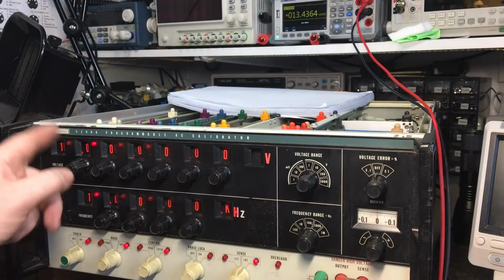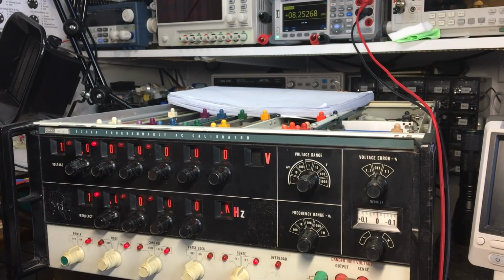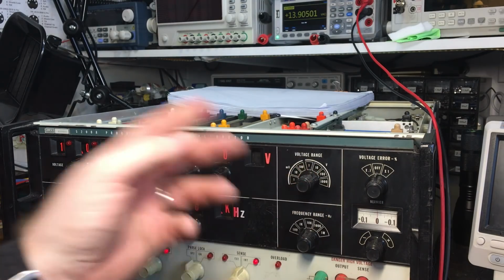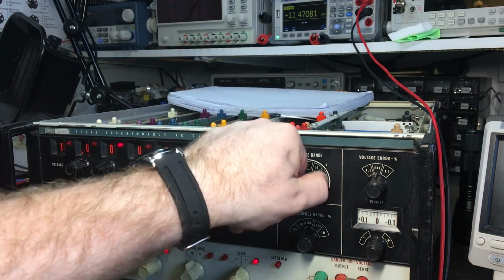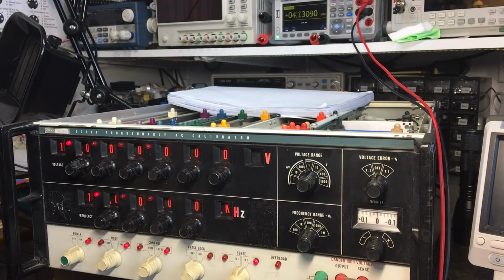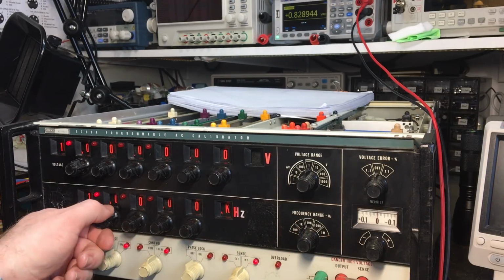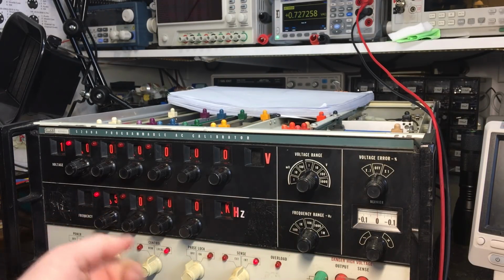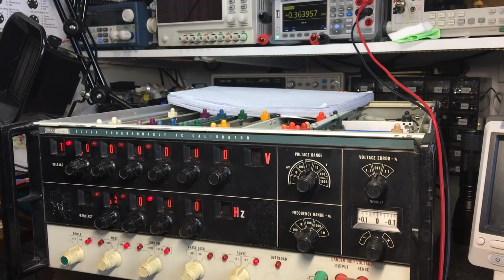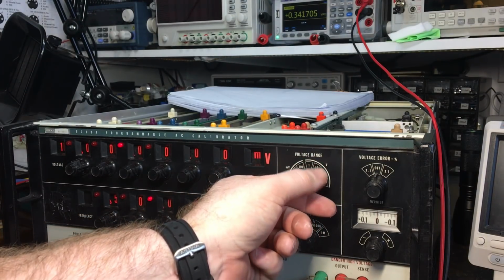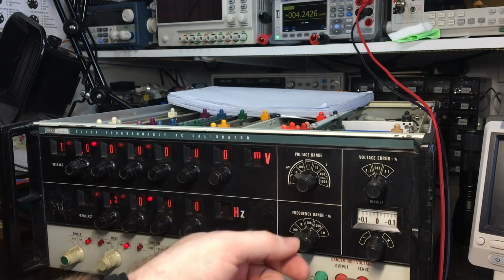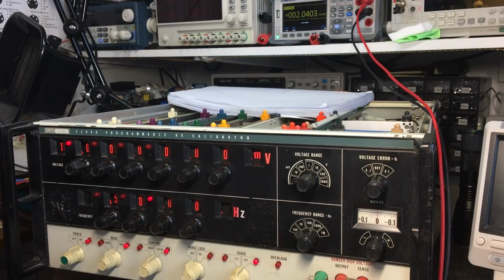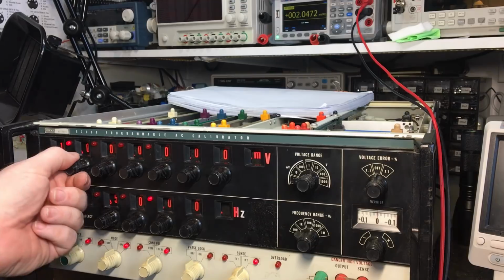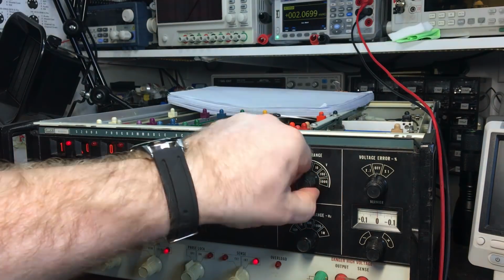So we've got a 10 volt range. 10 volts again, 8 out. 100 volts is very wrong. It's about 13 or so. It's flaking around a bit, so it's still got an issue there. But it is actually doing something now, which is a lot more than it was doing before. If I stick it back on, say, 50 Hertz, which I know this meter can definitely measure, you can see this voltage is a long way out from what it should be, but it is actually doing something. It's just wrong. So yeah, it's some progress at least.